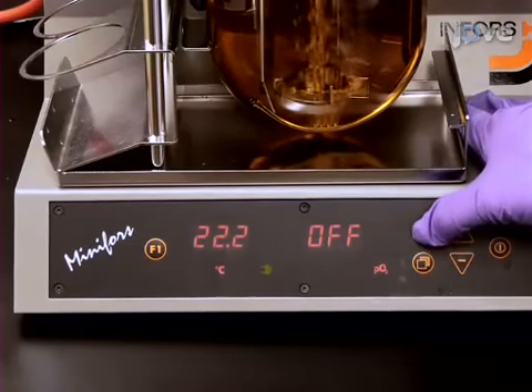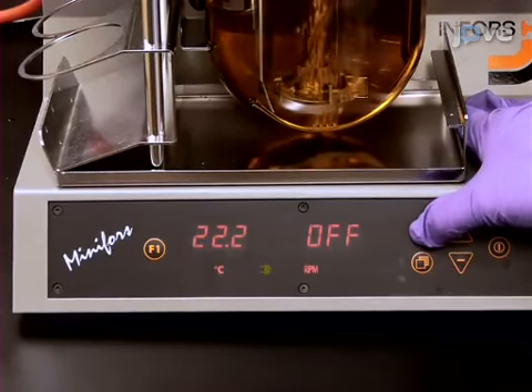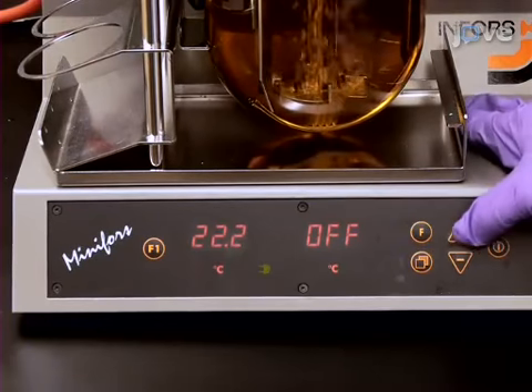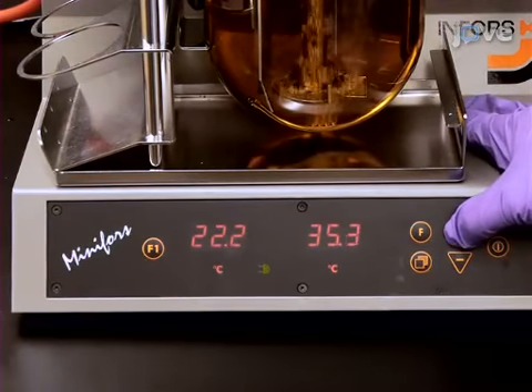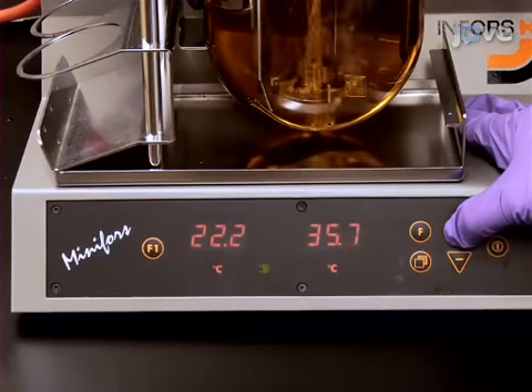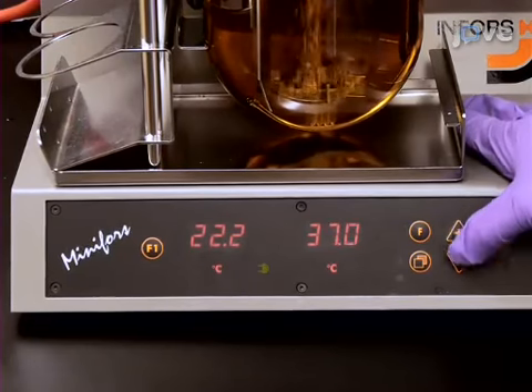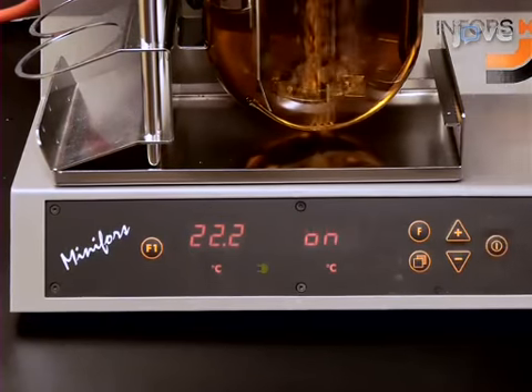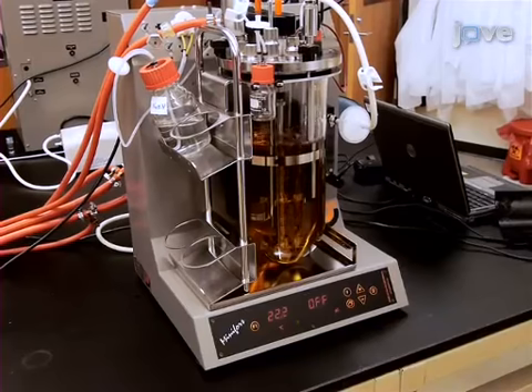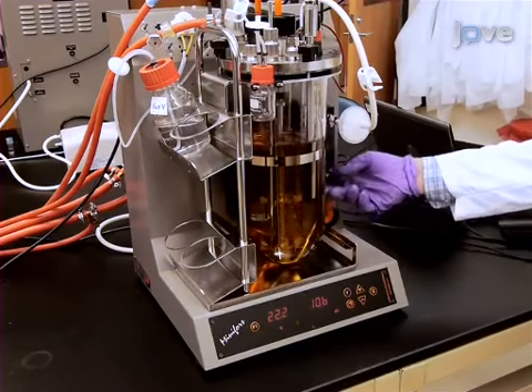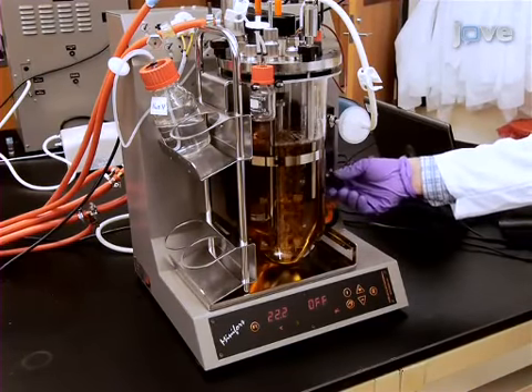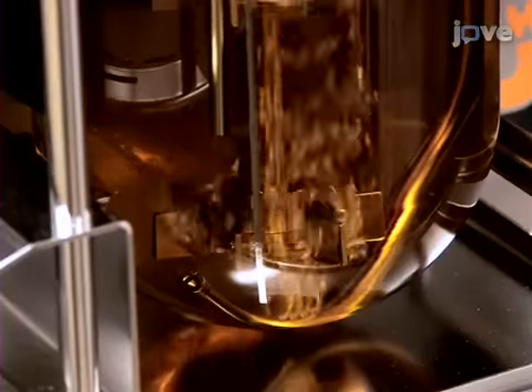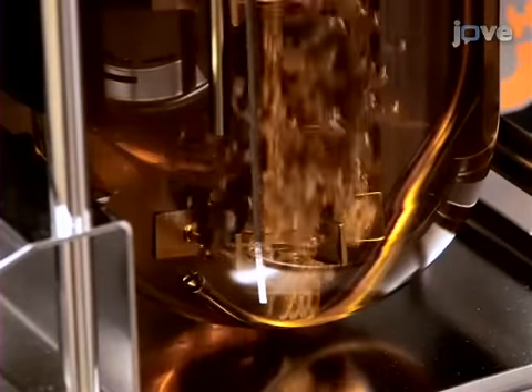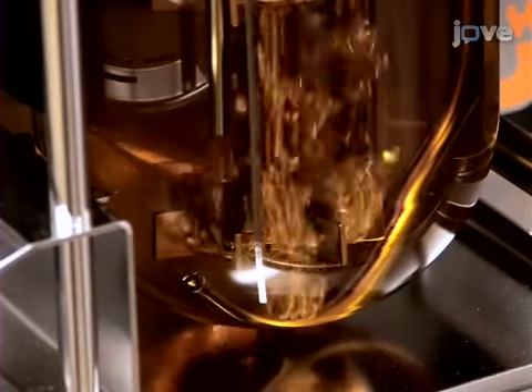Scroll to the temperature parameter and set the temperature to 37 degrees Celsius. Press the Enter button to start the temperature control. The vessel will heat up in 15 minutes or less. Turn the gas flow to 1 vessel volume of media per minute or less. For this setup, gas flow is 3 liters per minute. Bubbles should appear at the bottom.